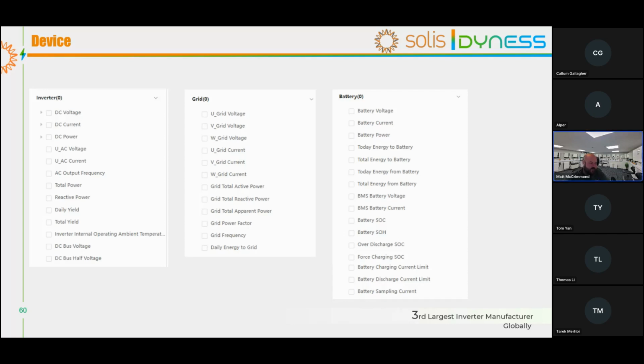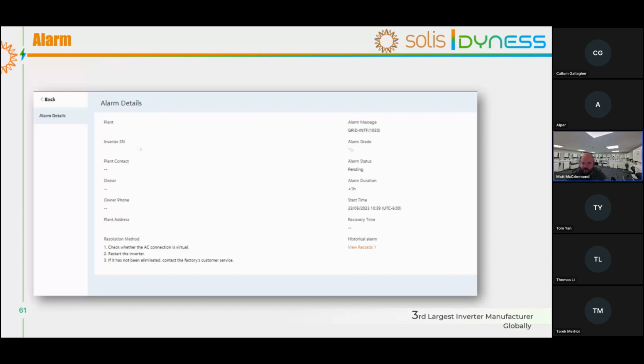So that's most of the stuff we do from our side. So we take all this information, and depending on what the alarm is, we look at the timestamp, which again is hugely important when you set up the inverter. You have that set correctly so that we can understand exactly what's happened, when it's happened. So this is the alarm message that the customer will see. So if they had, for example, grid interference, it'll tell you how long it happened for, when it happened, and then it'll give you some key indicators to understand what you should maybe do. From our side, we then go into the alarm, check the grid, check the values at that point to see if there's anything untoward that we can see. And that's how our process works for fault finding.